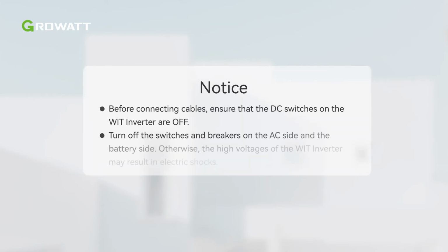Notice: before connecting cables, ensure that the DC switches on the WIT inverter are off. Turn off the switches and breakers on the AC side and the battery side. Otherwise, the high voltages of the WIT inverter may result in electric shocks.